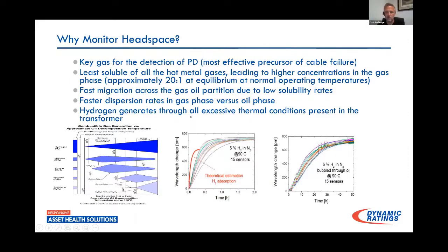So lastly, just to go through what's hydrogen, and we talk about hydrogen works a little differently when we're looking at gaseous state versus in oil. So one of the things is how quickly it disperses and the higher concentrations that we see in gas. So we have a much quicker dispersion rate occurring. We have a much higher concentration of the gas present, which leads to earlier detection and more reliable detection, because we're not counting on that convection of oil to get that hydrogen gas around to wherever our sensor location is mounted. When it hits a gas space, it's a pretty even dispersion across that gas blanket.